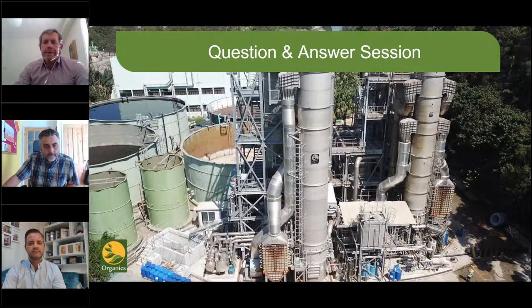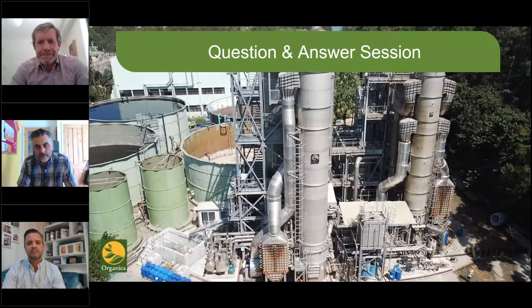Okay, and how do we control NOx emissions? NOx emissions, well, using the oxidizer. Yes. With thermal destruction of ammonia, it is a danger because one of the combustion routes for ammonia is to NOx. It's a kinetic process. It either goes to NOx or it goes to water and nitrogen. So you do have to control it carefully.